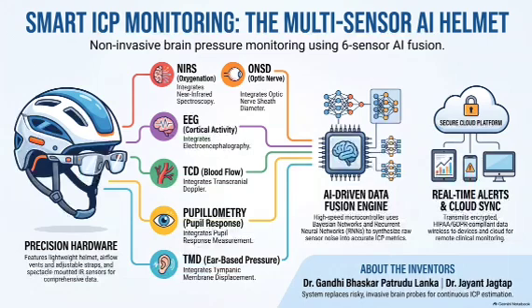That is the defining challenge of multimodal sensors. Raw data is entirely useless without context and synthesis. So the moment you turn the system on, it goes through a rigorous processing pipeline. Okay, what does that look like? First, it initializes and verifies that every single sensor is functioning, and it establishes a baseline calibration for the patient. Once calibrated, the system begins acquiring synchronized data from all 6 sensors. I imagine the synchronization, the timestamping is critical here. Oh, it is the glue that holds the whole concept together. Think about a heartbeat. When the heart pumps, it drives a spike in blood flow to the brain.